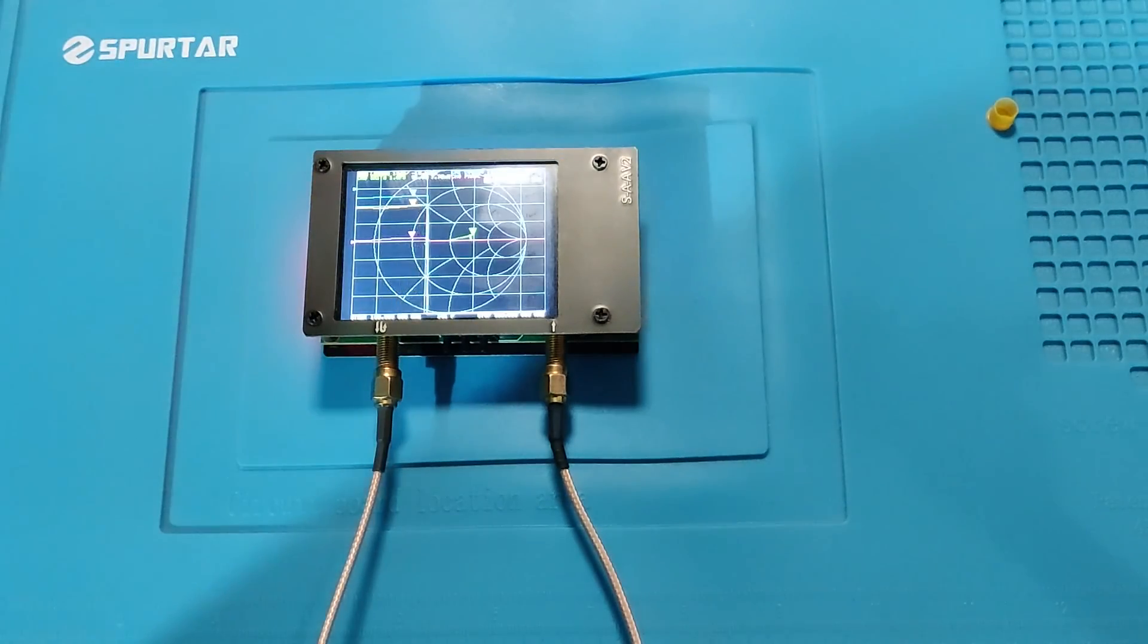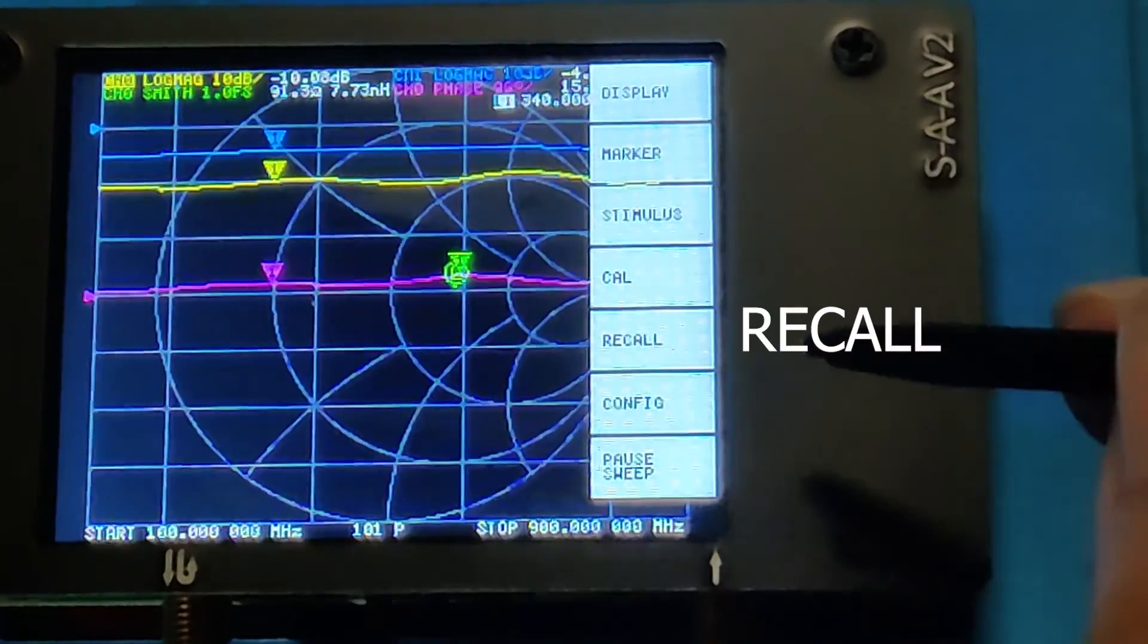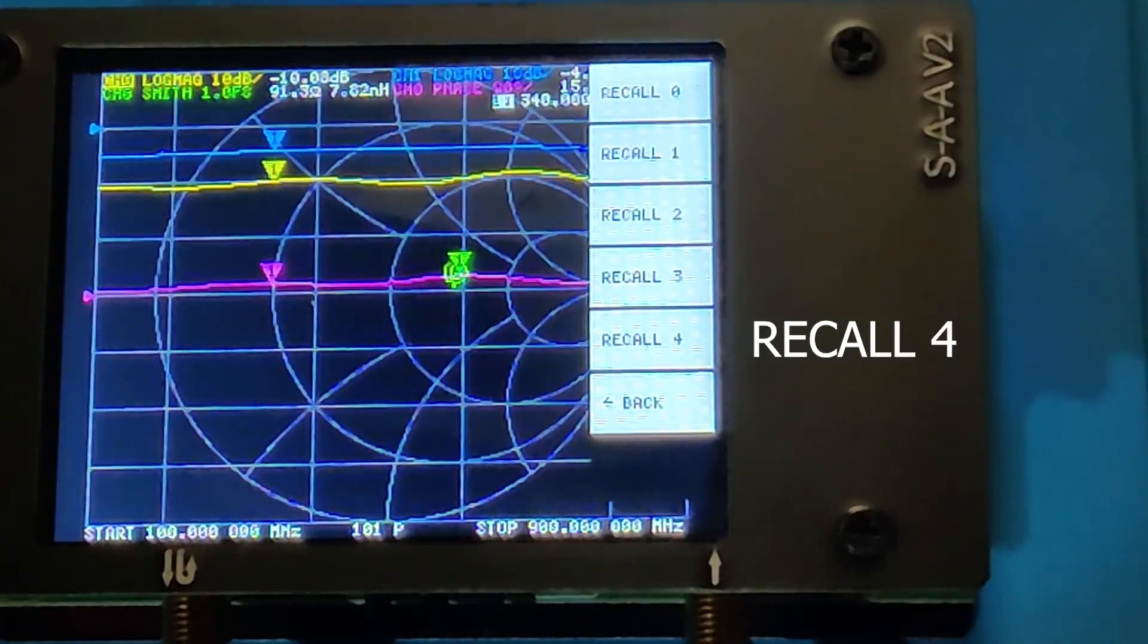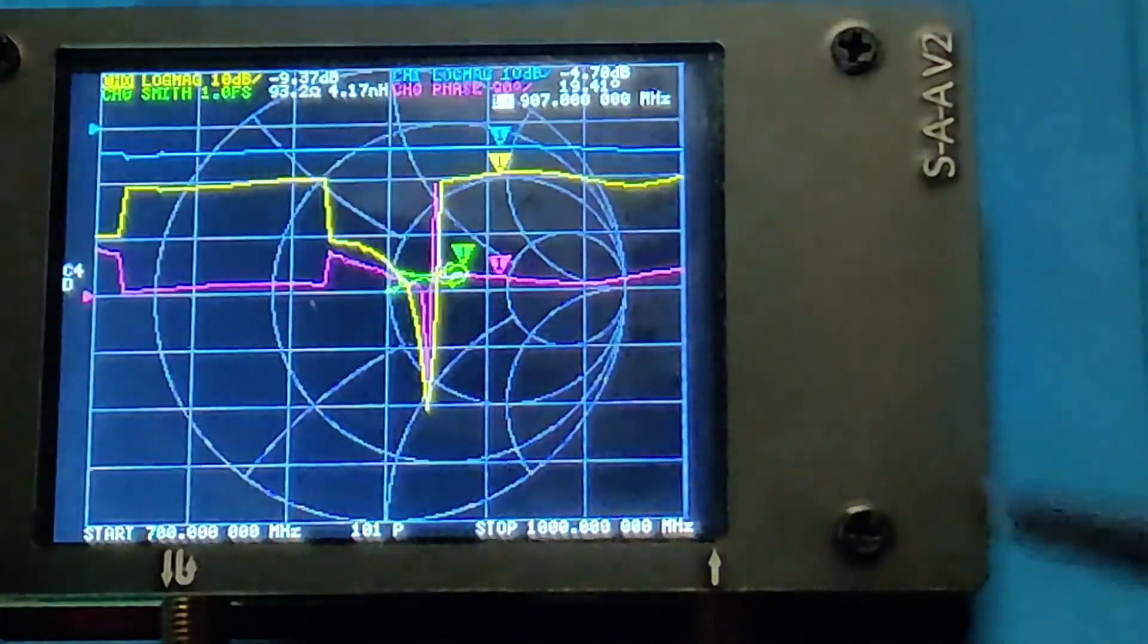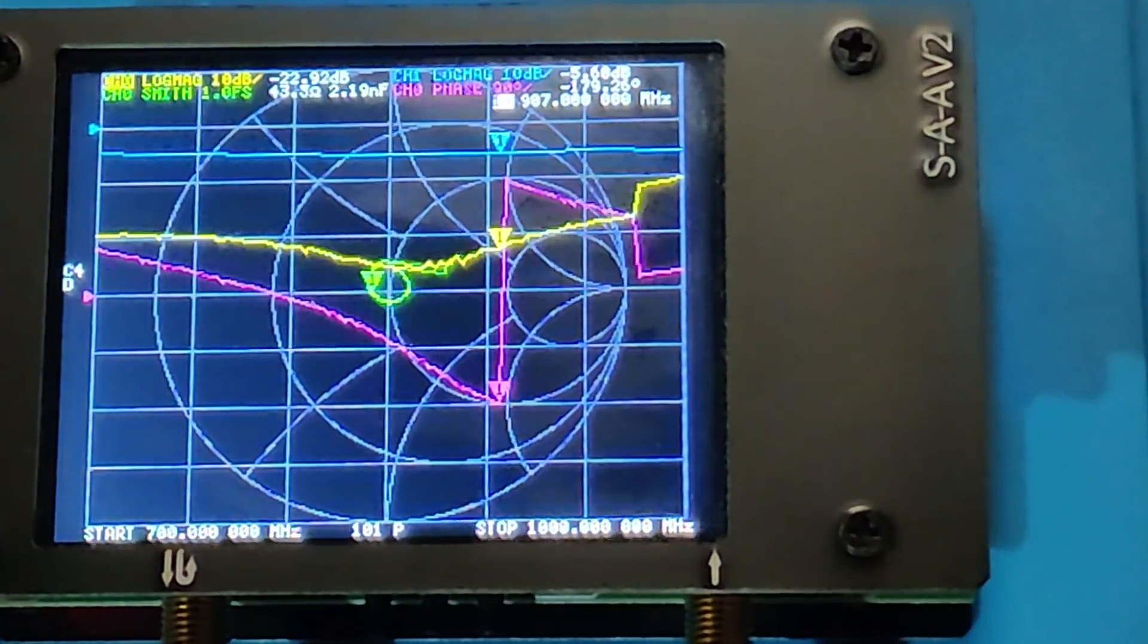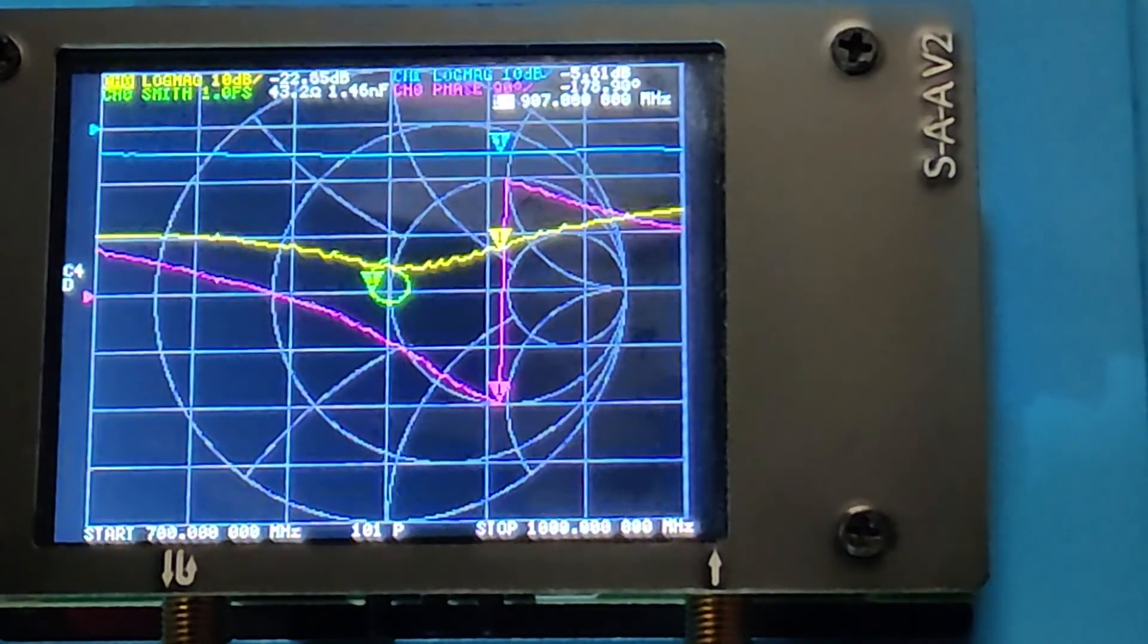I will click on the screen on the right side to open up the menu. Click on recall and then click on recall 4. This was the memory location in our previous video where we stored the S11 calibration.